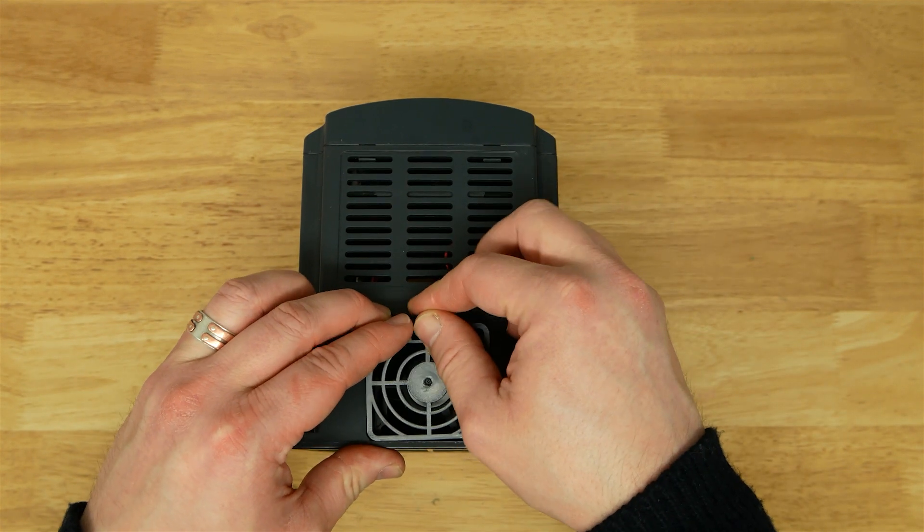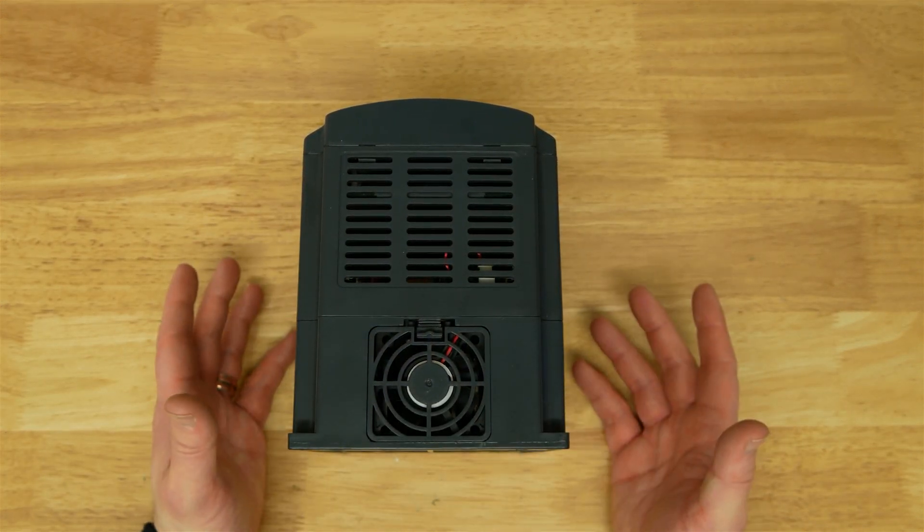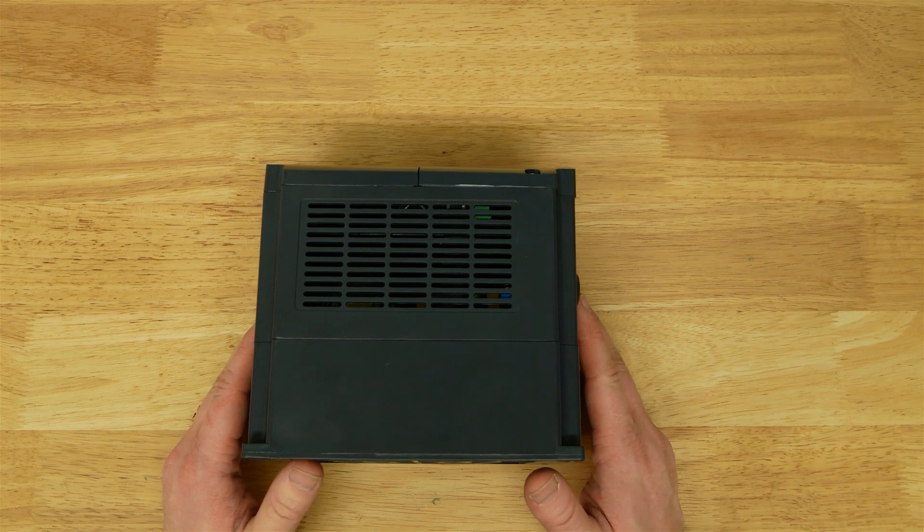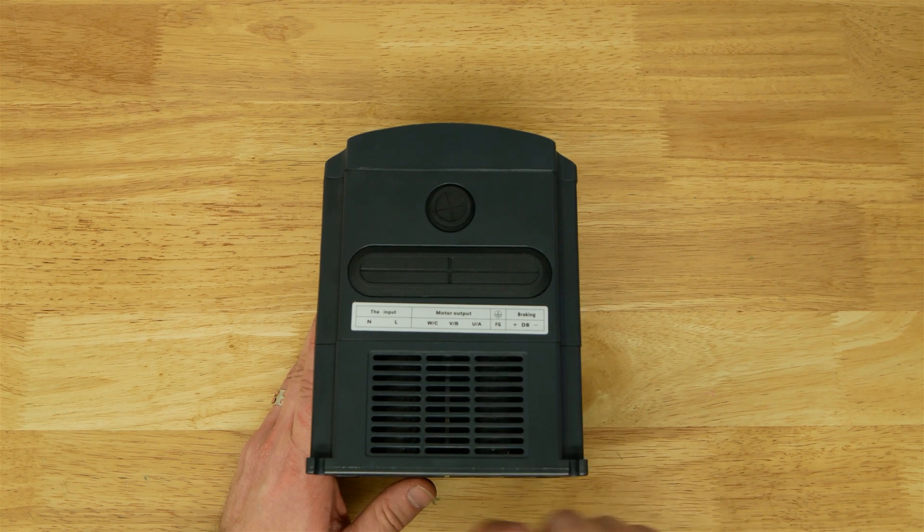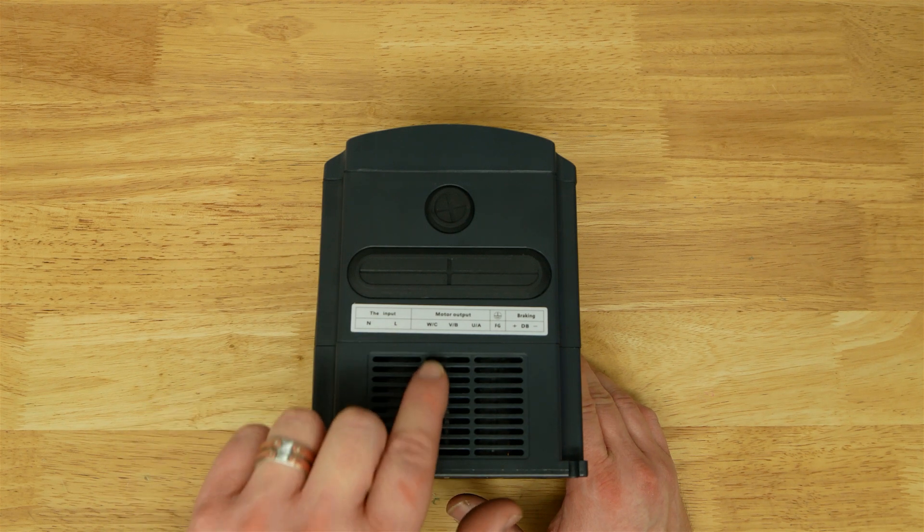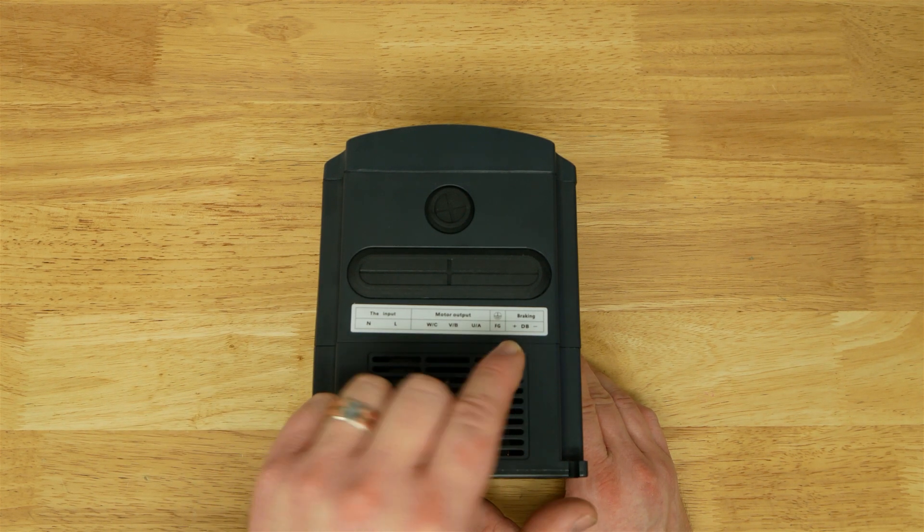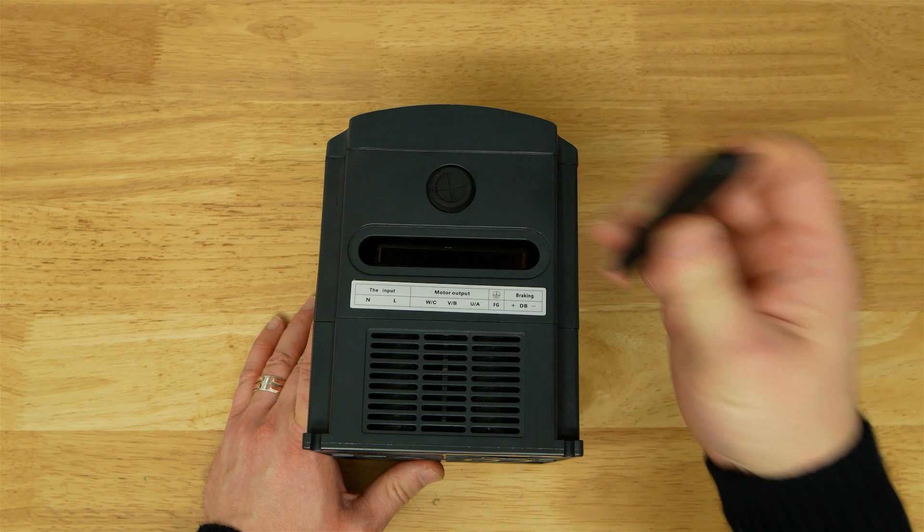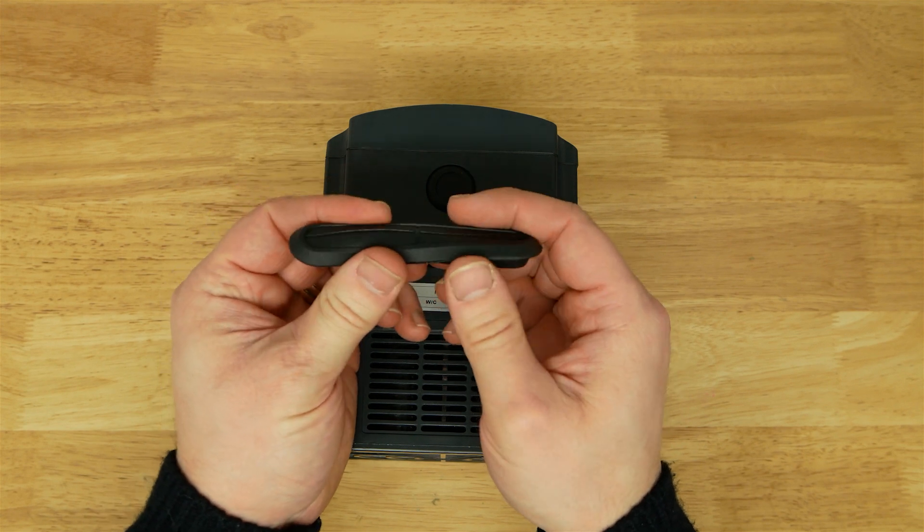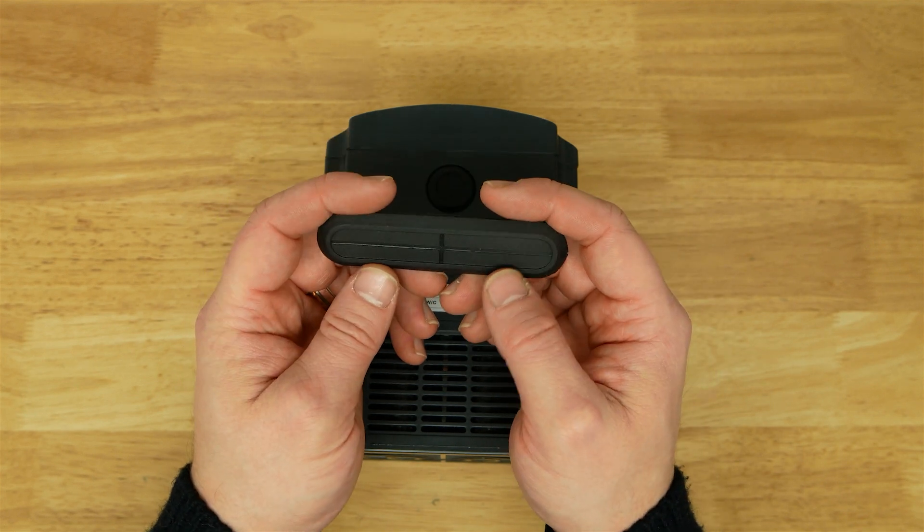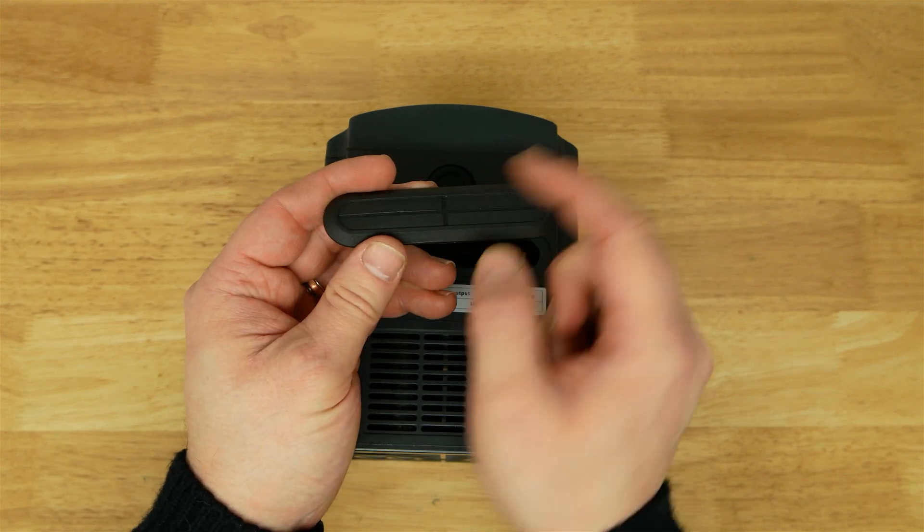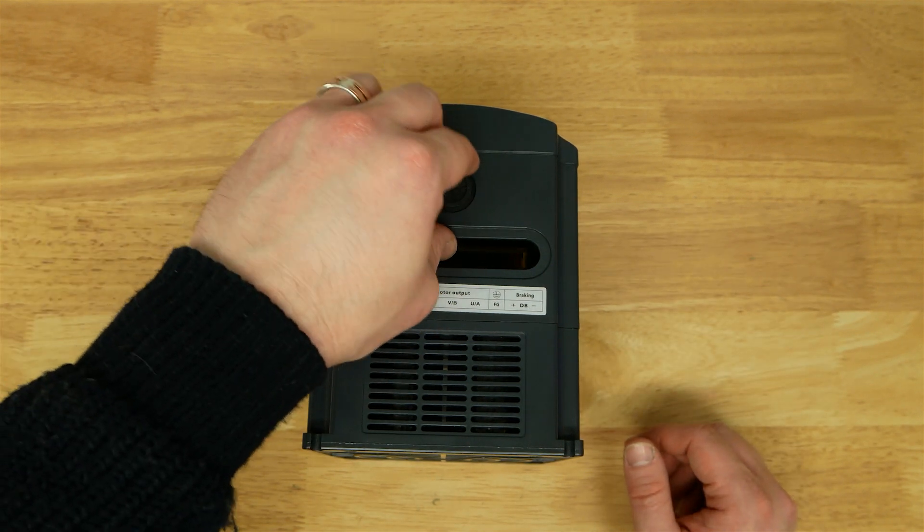You can pop the fan out and that reveals the heatsink below, a fairly chunky bit of aluminum. My other VFD is all metal at the back, all heatsink. Not so with this one. But to be fair, this is a 2200 watt unit and we're only using it on a 1100 watt motor. We've got 100% headroom. These cable entry grommets are quite nice and soft. You could cut across those lines and use that as a cable entry.